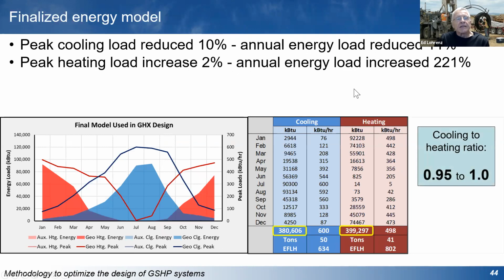The final model that resulted, when all the changes were built into the building and some changes that were asked for by the owners, changed the loads quite a bit. They implemented many of the recommendations that the previous energy models had shown, and that really helped improve the energy balance. So now we're looking at 380,000 kBTUs annually that we're rejecting to the ground or taking from the building. And we need to supply just under 400,000 kBTUs annually. So it's just under a 1-to-1 ratio.